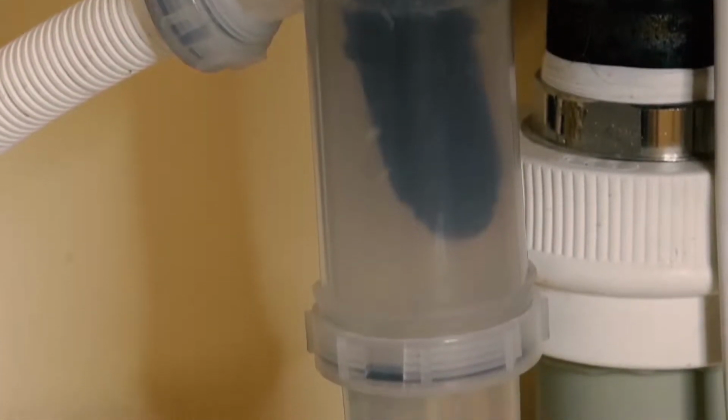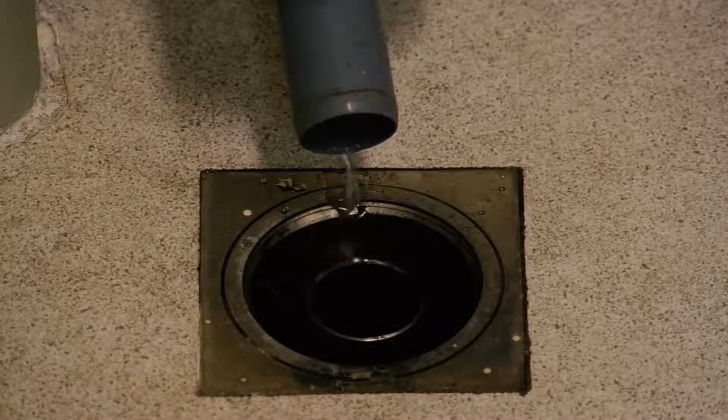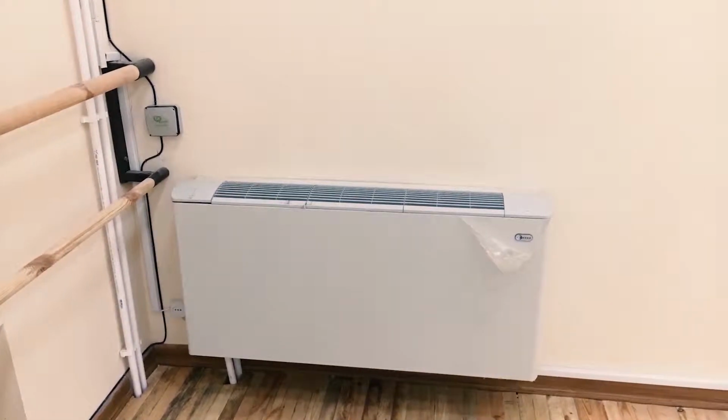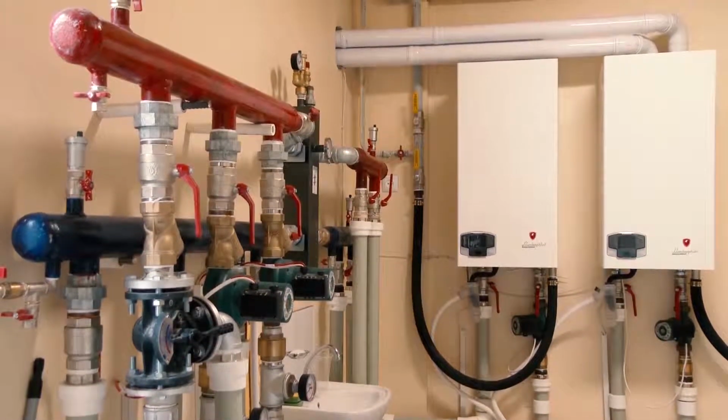Here we have applied advanced technologies. We have installed condensing boilers which, depending on the operation regime, can ensure up to 15% additional energy efficiency as compared to standard boilers. They use a latent heat in combustion products and fumes. Furthermore, we have installed fan coil units and locally adjustable heating radiators. With the help of all these measures, we achieved great energy savings, resulting in further greenhouse gas emission reductions by approximately 250 tons of carbon dioxide annually.